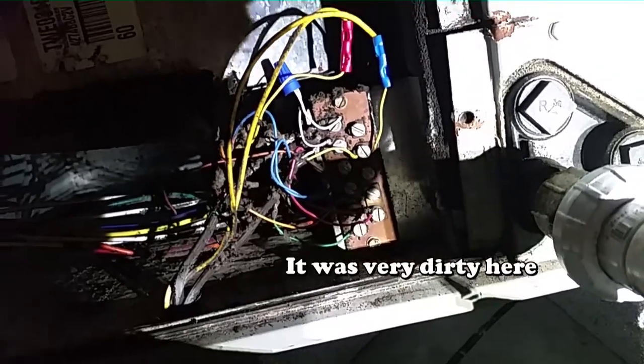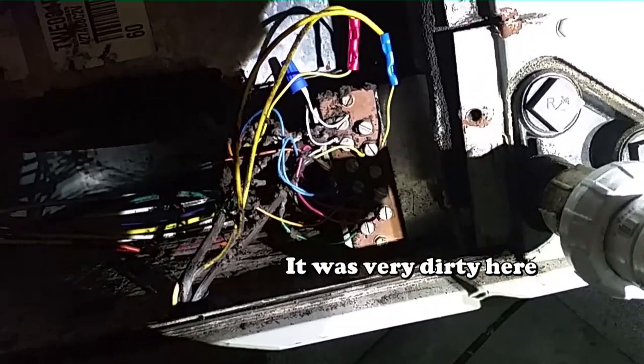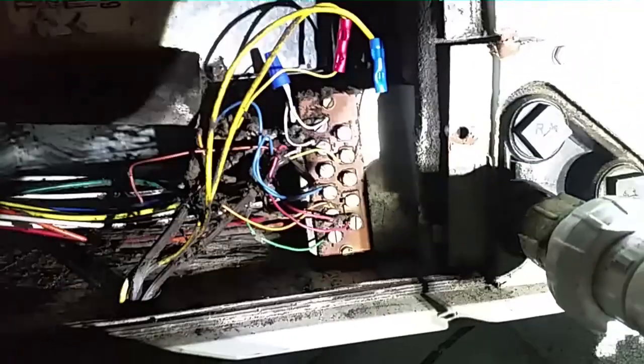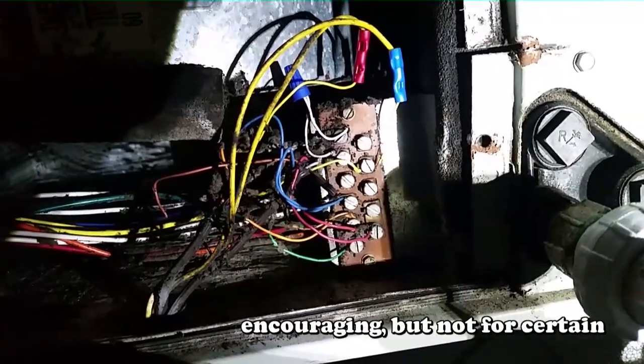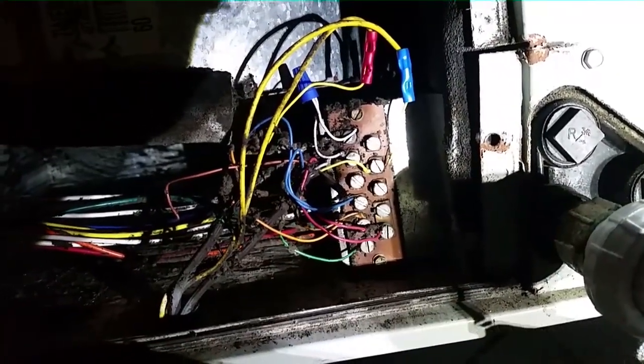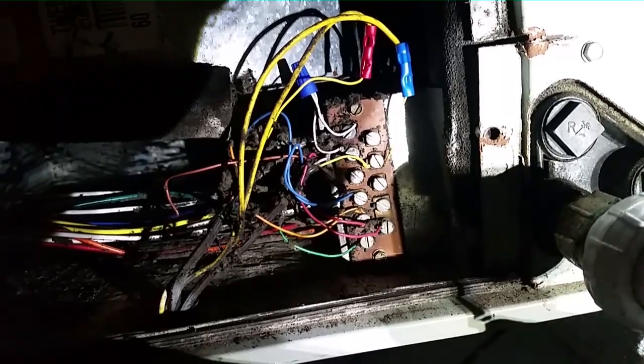Guys, I remade the connections on the Y wire. We should be good to go there. We should not lose signal here at the air handler if that's what happened actually. It's hard to tell. One of the connections did break off when I took it off, so it might have been weak or loose or something like that. So that's encouraging, but we will see. We're going to start it back up and let it run for a while, and I'm going to get out of this attic because it's hot.